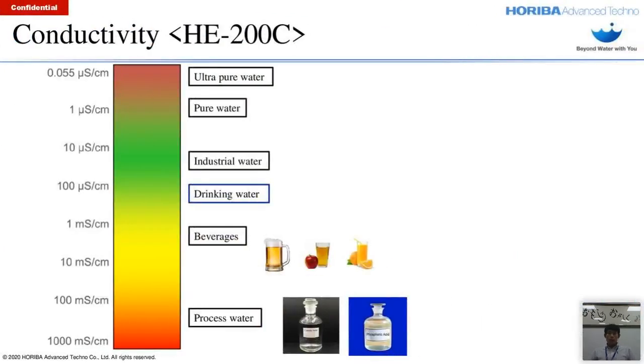All right, this figure shows the various ranges of conductivity. From the top to bottom, the lower the conductivity, the lower the concentration of impurities such as ions present in the water. For drinking water, the conductivity level should be around 100 microsiemens per centimeter, as you can see marked in the blue text box.